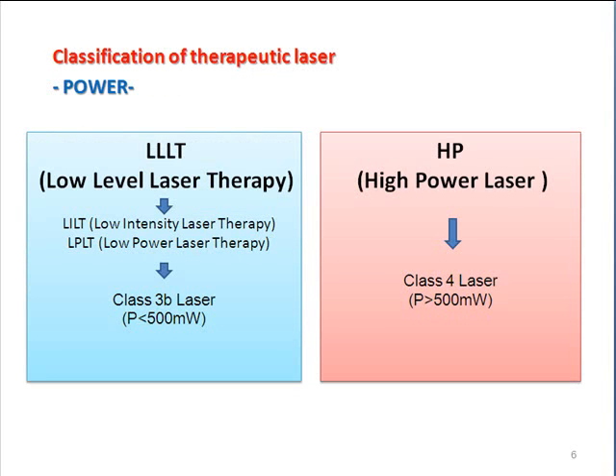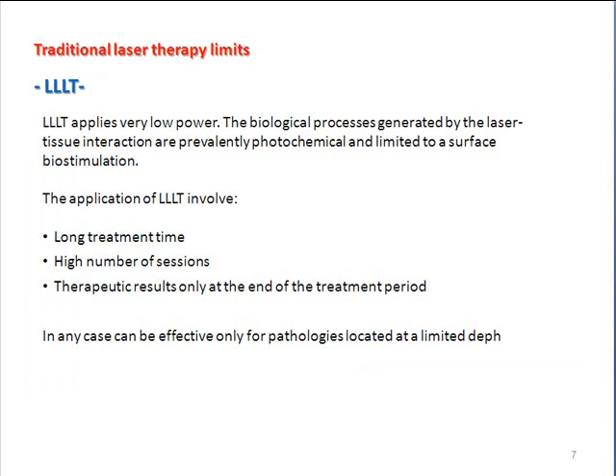Classifications of lasers are also based on power. Less than 500 milliwatts is known as low level laser therapy or LLLT. Greater than 500 is your class 4 lasers or high power. The class 3B lasers are below 500 milliwatts. Low level laser therapy applies very low power, so the application involves longer treatment times and a higher number of sessions.